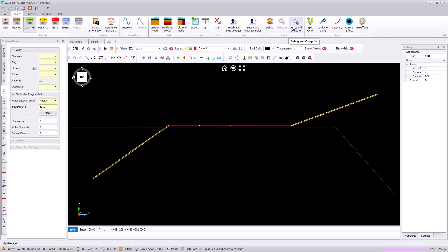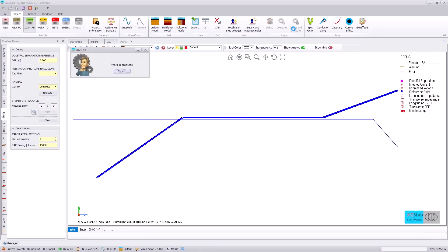Now we will go to debug and compute. At this stage the software will evaluate that all conductors are independent and not overlapping, and evaluate the inductive coupling, conductive coupling, and capacitive coupling that may occur from your transmission line to your pipeline or other metallic structures.